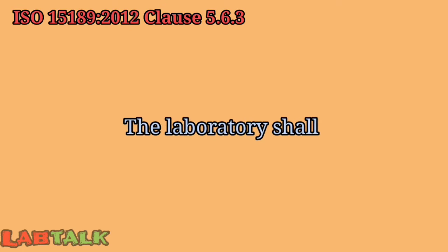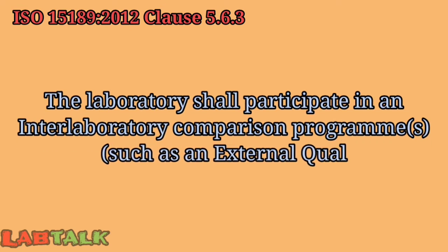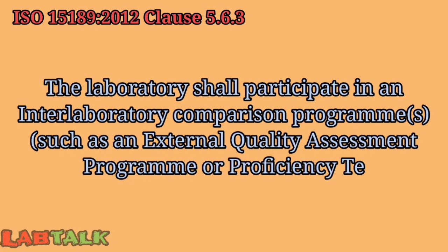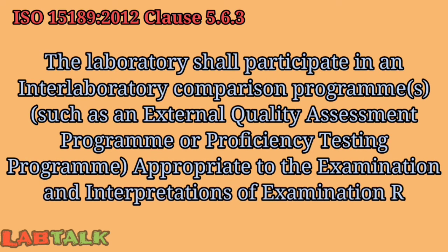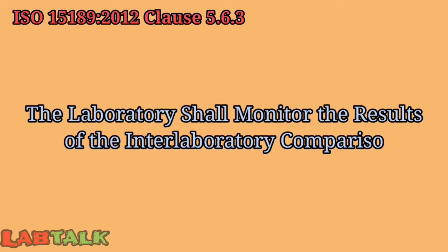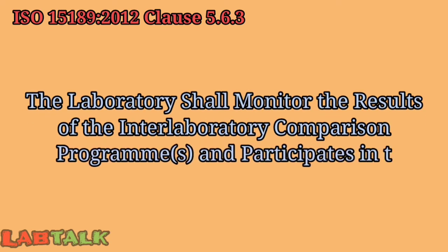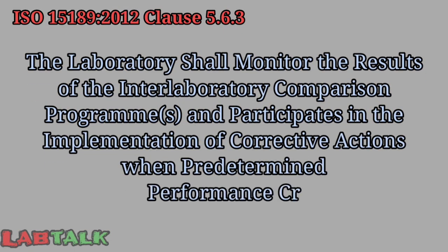Now, as per ISO 15189:2012 clause number 5.6.3, the laboratory shall participate in an inter-laboratory comparison program, such as an external quality assessment program or proficiency testing program, appropriate to the examination and interpretation of examination results. The laboratory shall monitor the results of the inter-laboratory comparison program and participate in the implementation of corrective actions when predetermined performance criteria are not fulfilled.